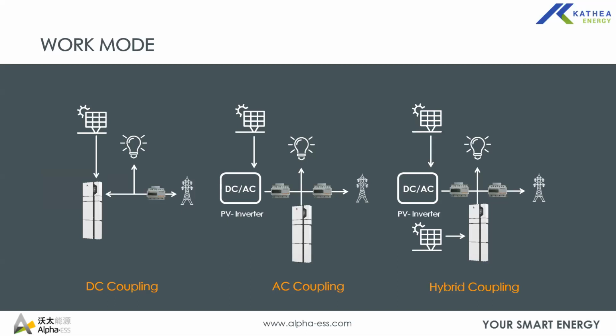When you have a second inverter on the system, and you are not intending to put in any PV to the Alpha system, that system is AC coupled. So basically from your DC mode, you would have your second inverter, which is called a PV inverter, and the PV array will be wired to that PV inverter, whether it's off grid or grid tie. So the system can be retrofitted to existing systems. If the client already has a grid tie inverter installed and is looking for a backup system, then you can just get an Alpha. There is no need to remove the existing system. You just wire it as an AC coupling.